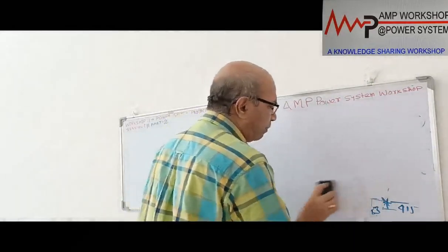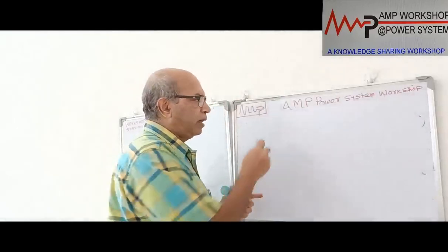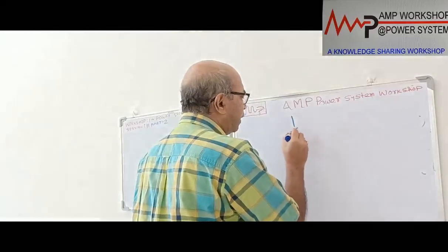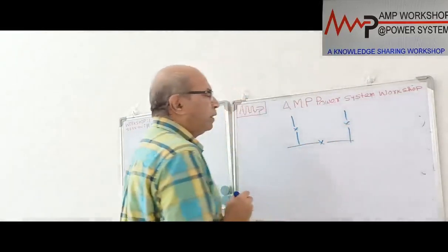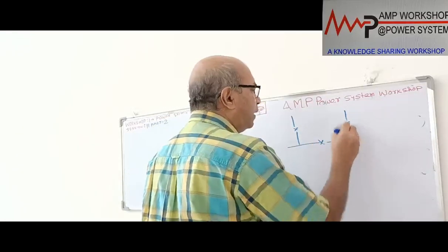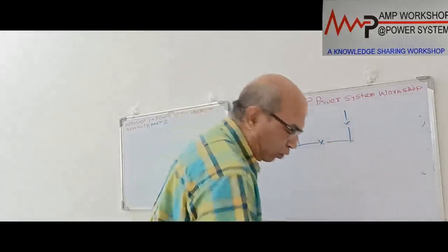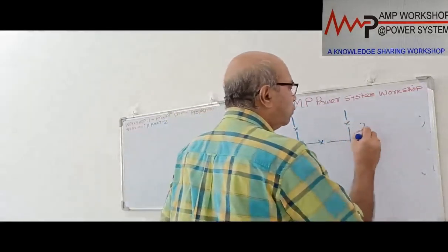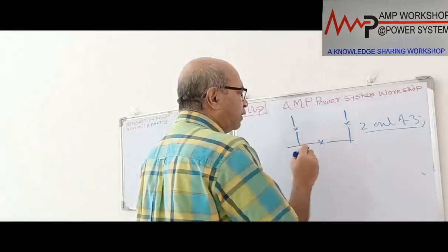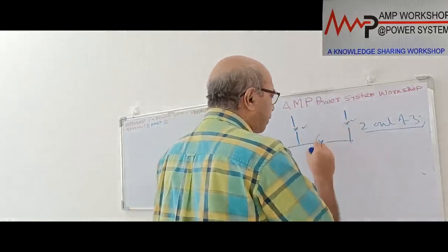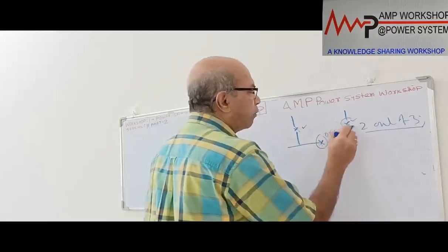Because when there is a fault on a bus section, normally the auto changeover scheme operates in case of parallel operation. Suppose this is a bus coupler, it is running in parallel. So if there is any bus fault, immediately it will operate. But in some schemes where an auto changeover scheme is present, it will be a 2 out of 3 scheme. In that operation, that means at any time out of these 3, 2 will be on. Either this incomer will be on with the bus coupler off, or one of the incomers with the bus coupler will be on, and the other incomer will be off.